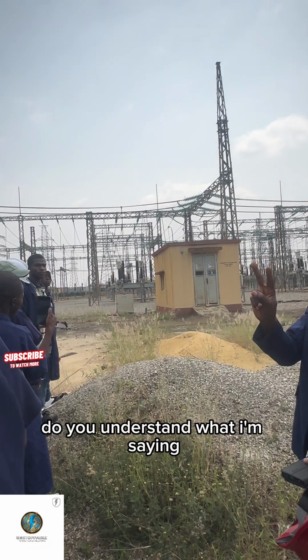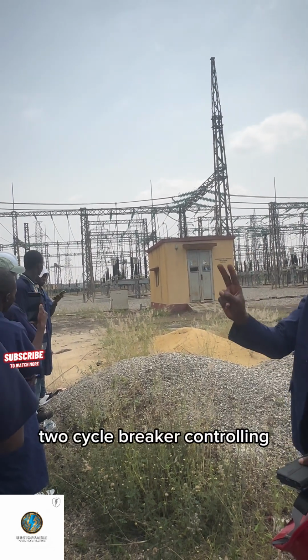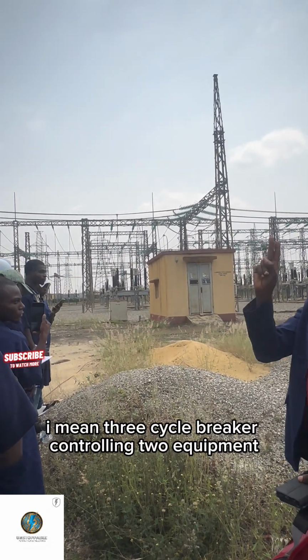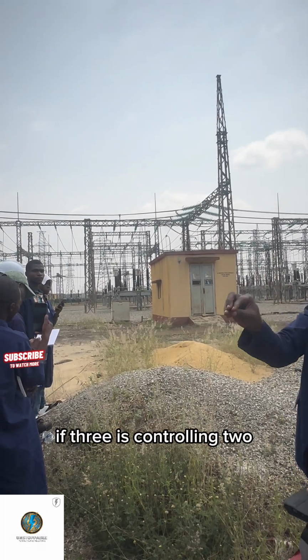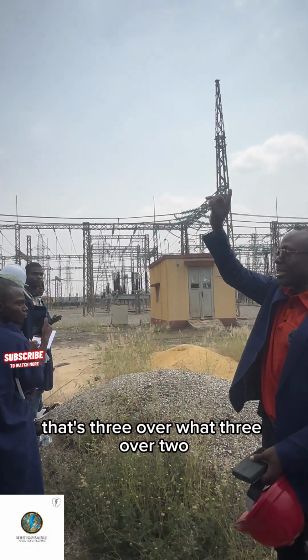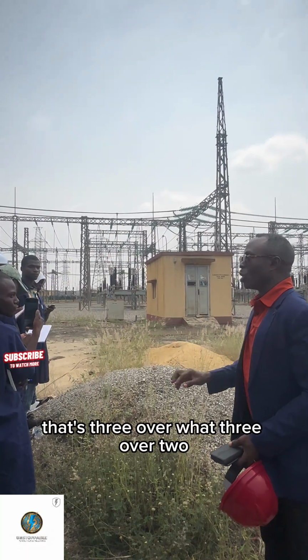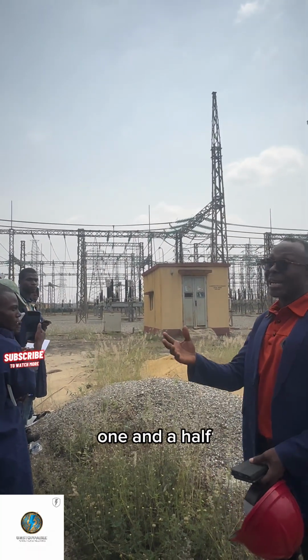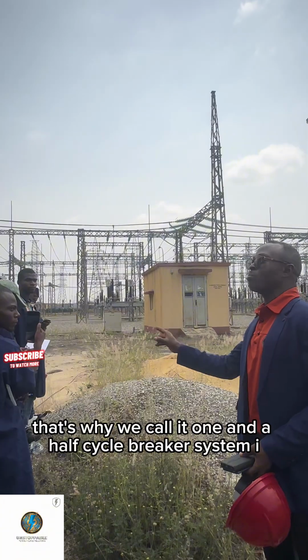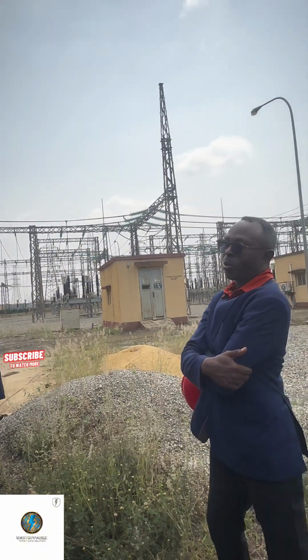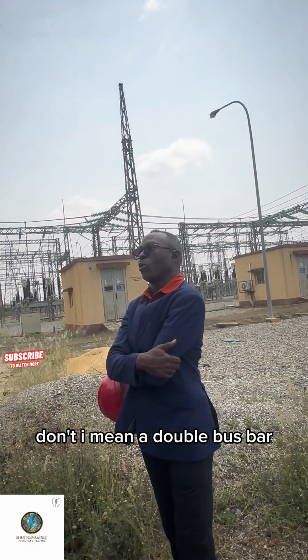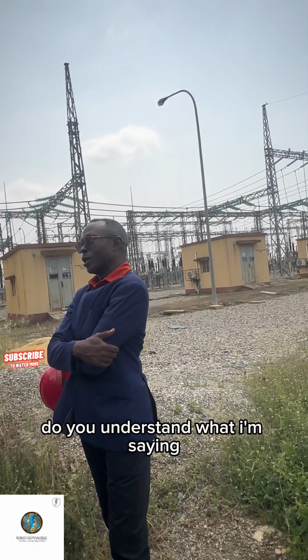Do you understand what I'm saying? 3 circuit breakers controlling 2 equipments. If 3 is controlling 2, that's 3 over 2. What is 3 over 2? 1.5. That's why we call it the 1.5 circuit breaker system arrangement of double bus bar. Do you understand what I'm saying? So go and read it.